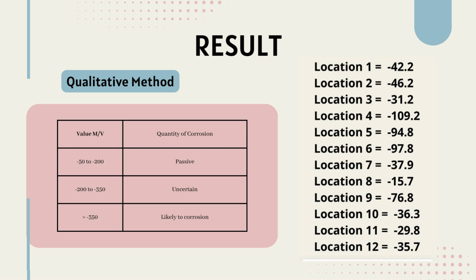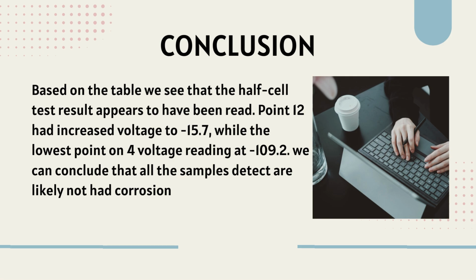Location 12 negative 35.7. In conclusion, based on the table, we see the half-cell test results that appear to have the highest voltage at negative 15.7, while the lowest voltage reading was negative 109.2, so we can conclude that all the samples detected are likely not corroded.